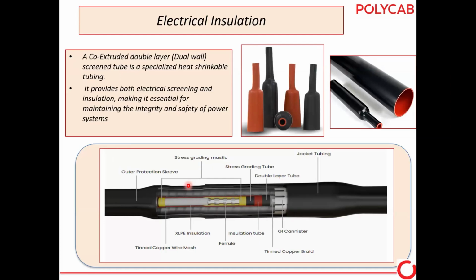Cable accessories are nothing but the cables. It is the preparation of the cable at site, I can say, or manufacturing of cables at site. So we are preparing the exact layers that the cables have. Like conductors are there, so we are using the ferrules or mechanical connectors. Like semiconducting layers are there in the cables, we are giving the stress control tubes and stress control mastic. Now XLP insulation is there, so we are using co-extruded dual wall tubes for the insulation purpose. Inside it is the insulation, outside is the semiconducting layer. So it provides electrical screening and insulation, maintaining the integrity and safety of the power system. So this is the electrical insulation. Like XLP insulation, we are giving the dual wall tubes.